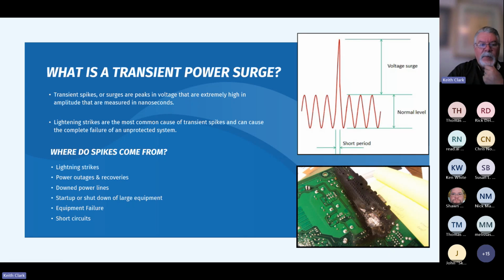So what is a transient power surge? Transient spikes or surges are peaks in voltage that are extremely high in amplitude, and they're measured in nanoseconds. This is a very, very rapid event. Lightning strikes are one of the most common causes of transient spikes. Anybody that lives in Florida will tell you that. There are other states also that have a lot of lightning activity, and it's become a standard in most of those places.